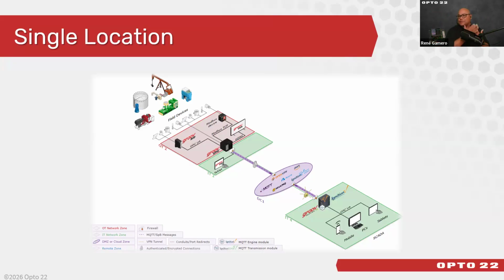This is edge-driven SCADA, meaning that when you've defined all those variables, all those tags you're talking to - whether physically to a temperature sensor, a motor, Modbus device, Siemens PLC, Rockwell PLC - at the moment it publishes its Sparkplug B to this broker, it's brought along with it all that contextualized data, so from your perspective screen you're just looking at all the devices out there publishing their data, and you're subscribing to them.